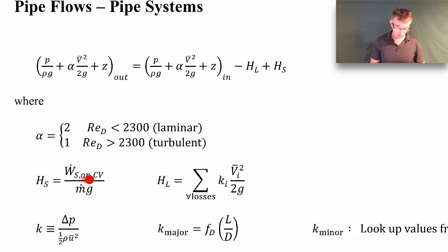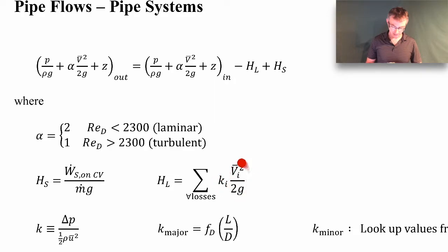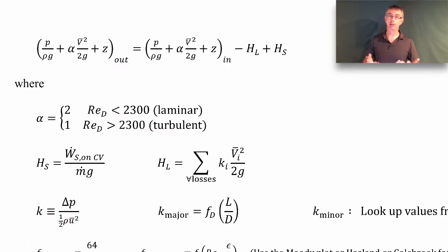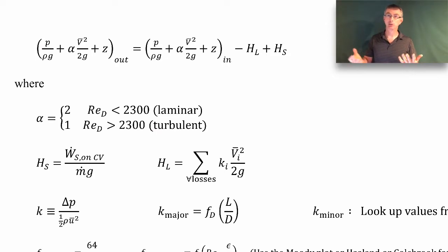If you're putting energy into the flow, such as with a pump or compressor, the shaft head is positive. If you're taking energy out, like a turbine, then it's negative. The head loss term is the sum of all the losses that occur in the pipe — for all losses, we have a loss coefficient times the velocity head where that loss occurs. The loss coefficient is defined as the pressure drop divided by the dynamic pressure, making it dimensionless based on the average flow velocity. For example, to find a valve's loss coefficient, you'd measure pressure at the inlet and outlet, measure the flow rate and cross-sectional area to get average velocity, then compute that dimensionless ratio.